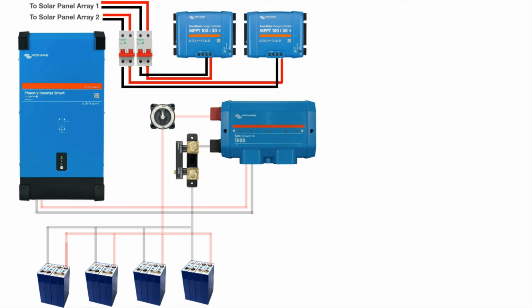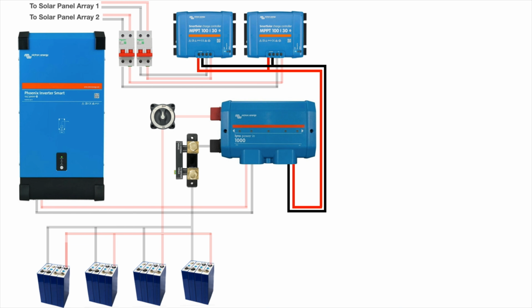So yeah, leave us a comment. So we wire them up like this. We've got 2 solar arrays - a ground solar array and a roof solar array. Just 2 panels on the roof, 2 panels on the ground at the moment. I've split it up so we've got 2 separate circuits. They come in from the roof and the ground into the 2 DC isolators. From the isolators they then go straight into the MPPT 100/30s. Then we come out of the MPPT straight into the Lynx power in, which in turn will then go into the batteries or into the van for usable power.